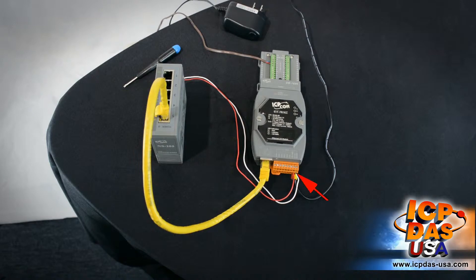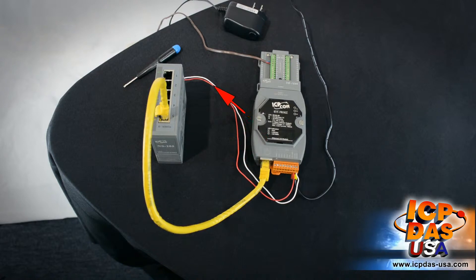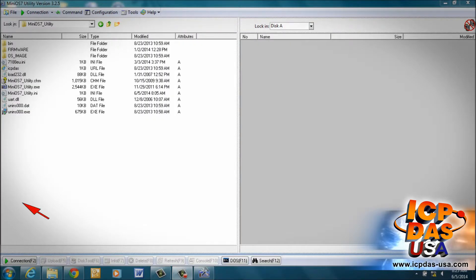We connect an Ethernet cable from the ET7018C to the NS205 industrial Ethernet switch. We daisy chain the power from the ET7018C to the Ethernet switch through the terminal block to power the NS205 Ethernet switch and share the same power supply. After everything is connected, we will use an Ethernet cable to connect our NS205 Ethernet switch to our PC.